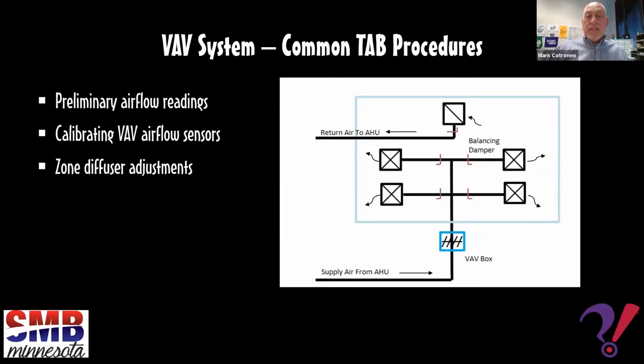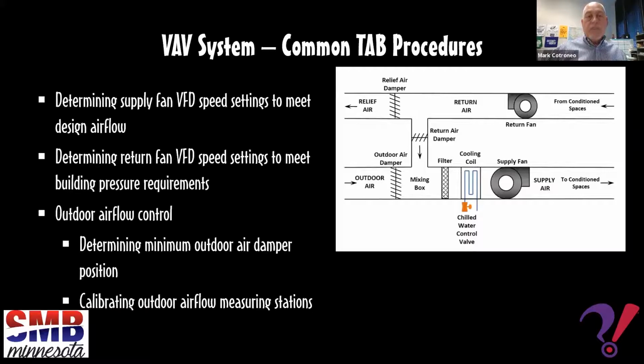Once all VAV boxes have been calibrated, enough of the boxes are indexed to their max set point to match the design for airflow of the supply fan. As Miles alluded to, the fan isn't really sized for the total system, but just the major portion of the system. So then the airflow is measured by a duct traverse, and the VFD is set to maintain the design airflow. The return fan and VFD are then measured and set in the same manner.